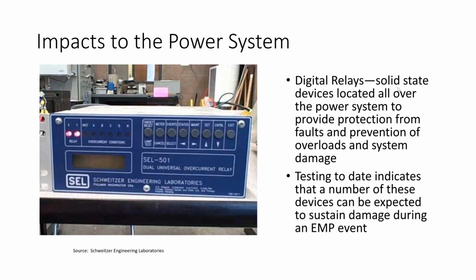And these things are located, I mean, all over the power system. There are thousands of these things on the high voltage and extra high voltage transmission system. Their job is to provide protection for the equipment that's on the power system. So let's digress a little bit from that. The relay tends to be at the end of the line in the sensing system. So there is a device that's out in the substation, out on the transmission line, that's taking a signal off the device or the line itself. It is bringing that signal back to this digital relay, and the relay is determining whether it's situation normal or a situation of a problem. If it's a problem, the relay will actuate. It will cause a trip signal to go out to circuit breakers. It will take the line out of service and protect the equipment and the line from damage from overloads or other kind of system damage. So that's the purpose of the device.